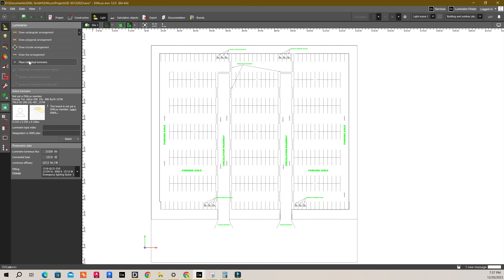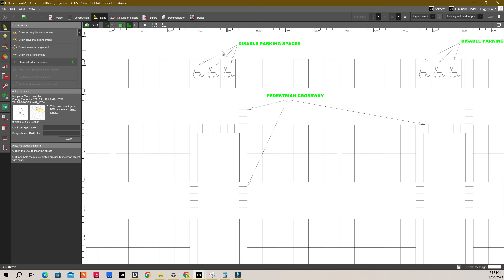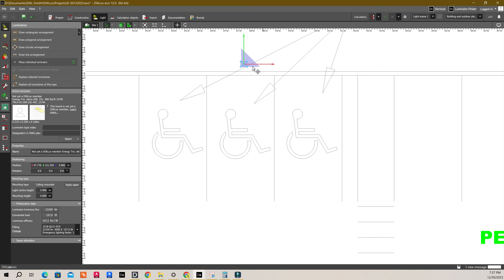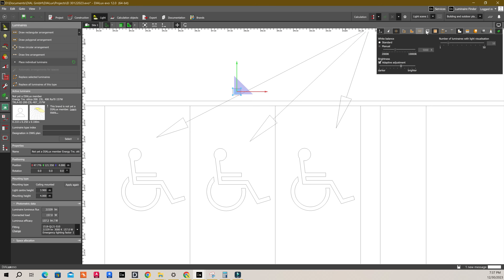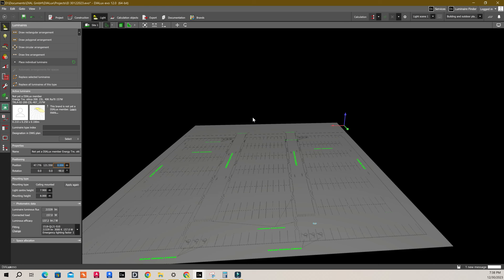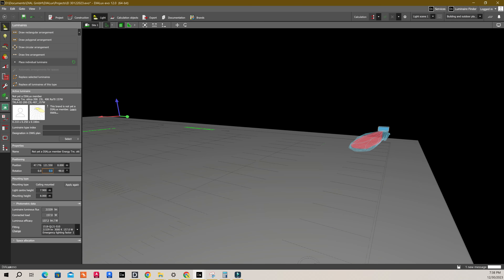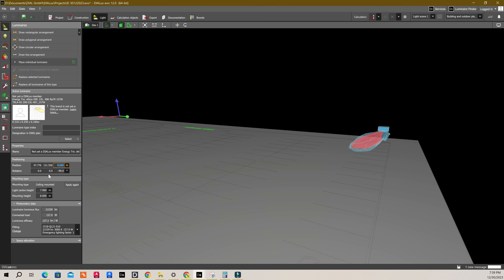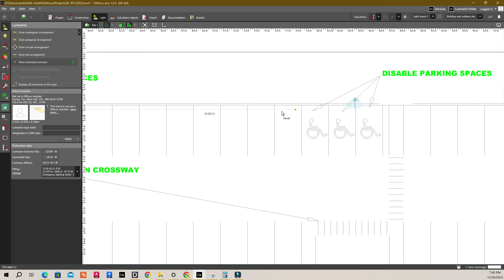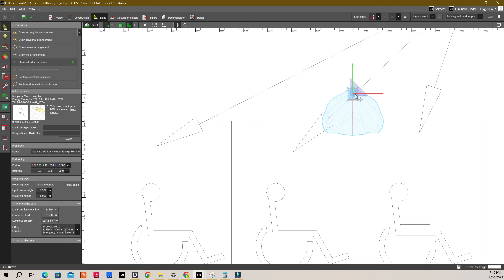Firstly, I will provide a dedicated light fitting for each disabled car park because there is a special lighting requirement for this. Place the light fitting here. You can use this option to see the curves of your light fitting. Rotate your light fitting, check the height and the angle as well. You can also check and change the parameters in the 3D view. I am going to change the height to 8 meters and the angle to minus 10 degrees. Copy the light fitting and paste it to the other disabled car park areas — make sure you double check the rotation, tilt and height as well.